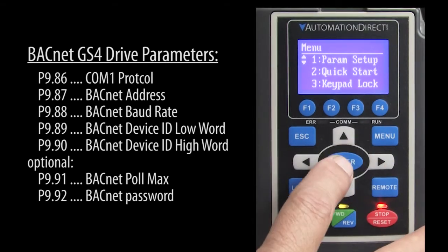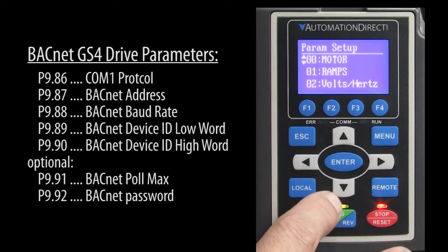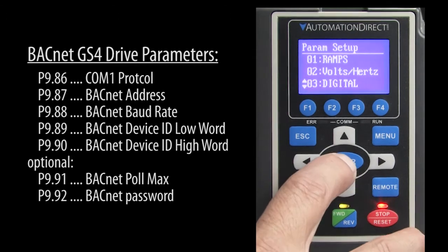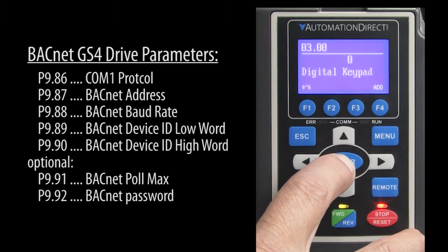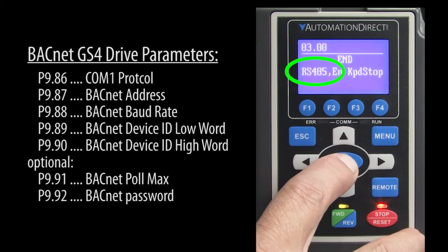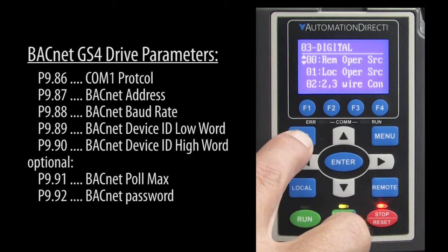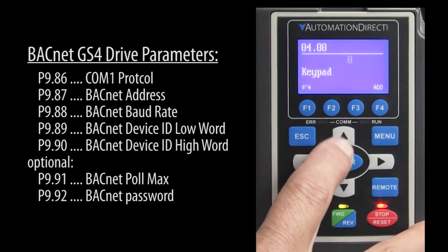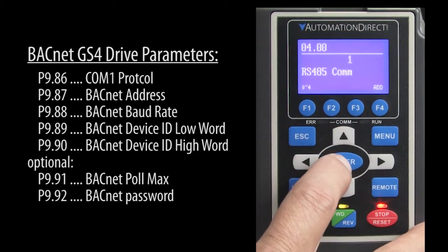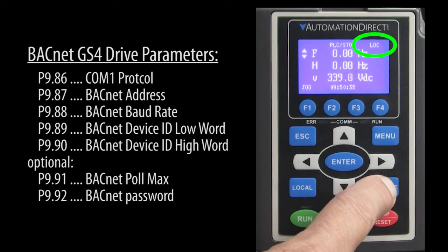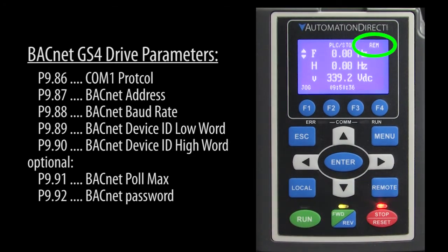And of course, to control and monitor the drive via BACnet, we need to make sure parameter 3.0 is set to accept commands via RS-485, parameter 4.0 is set to accept frequency values via RS-485, and that the drive is in remote mode.